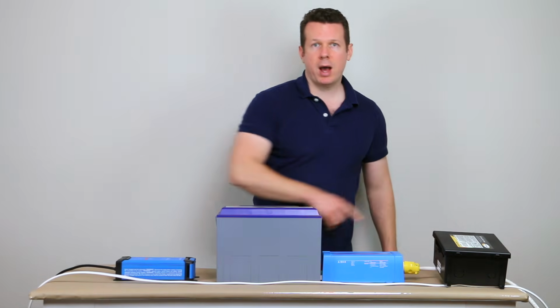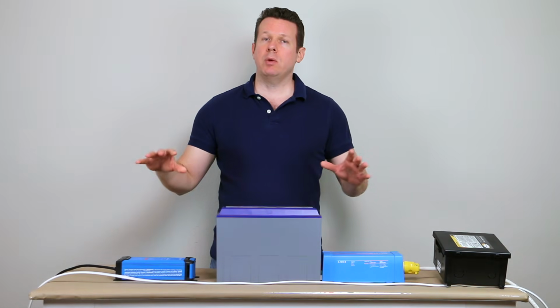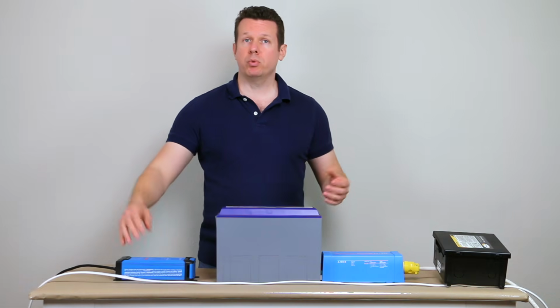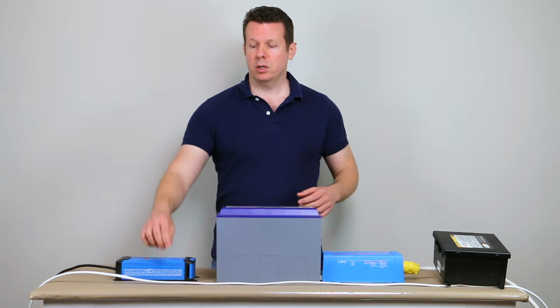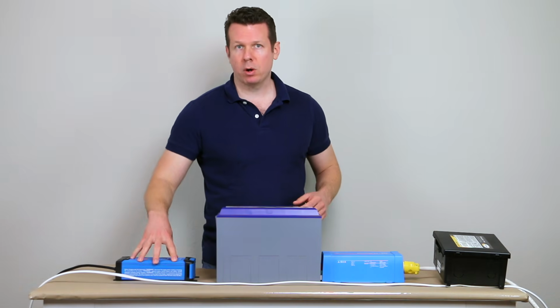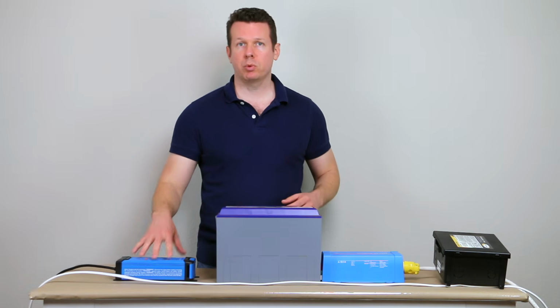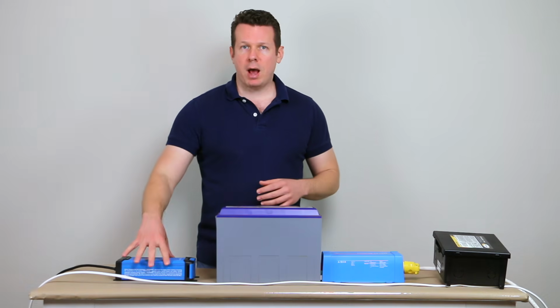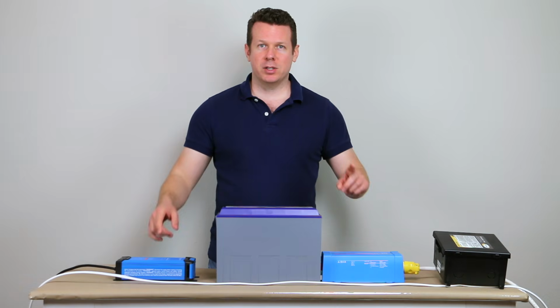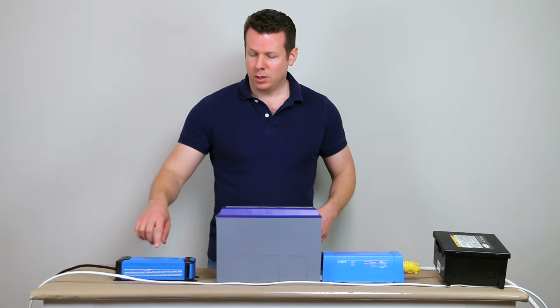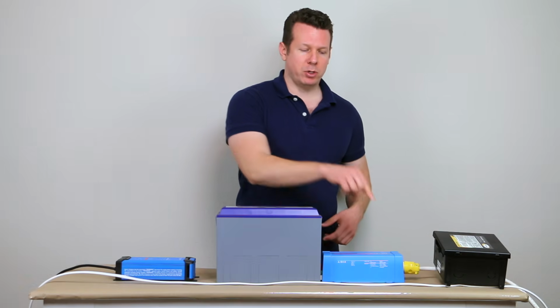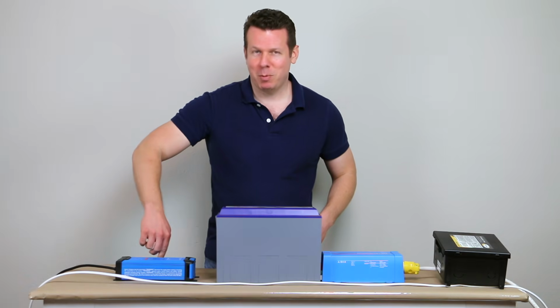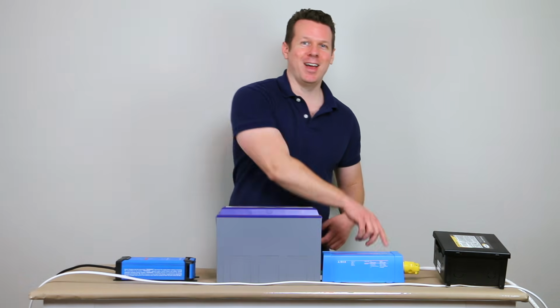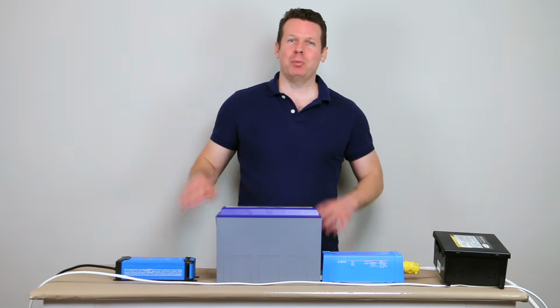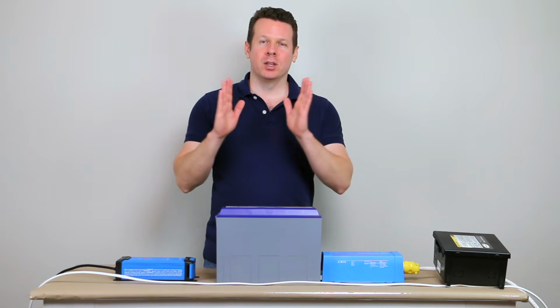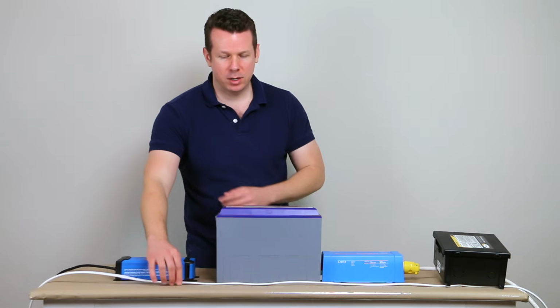We can also loop back and tie our charger in, making sure the charger only runs when you're tied into the power grid. So when this powers up, it'll power up your charger, and when this goes dead, the charger goes dead too. You don't want to tie your charger in with your inverter, because that would create a loop: the charger charges your battery, which powers your inverter, which would power your charger. We don't want to create that loop, so the charger is only tied in with this line.